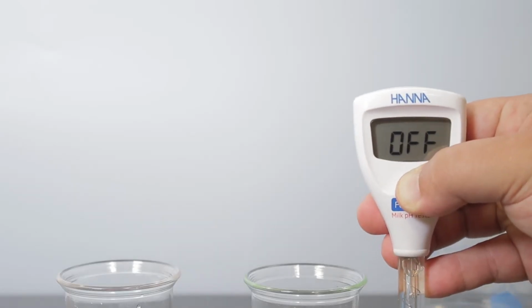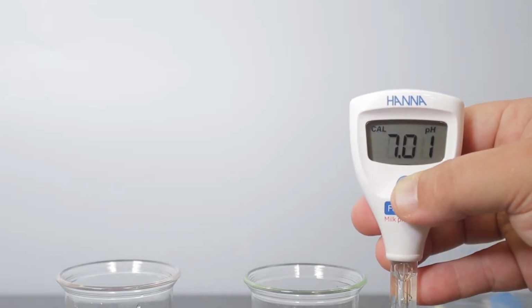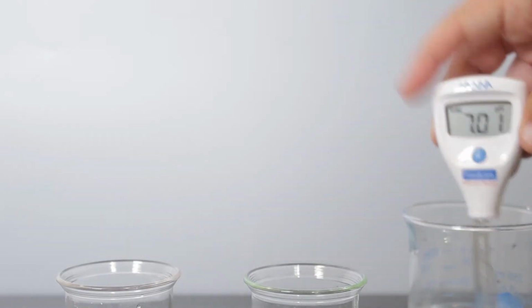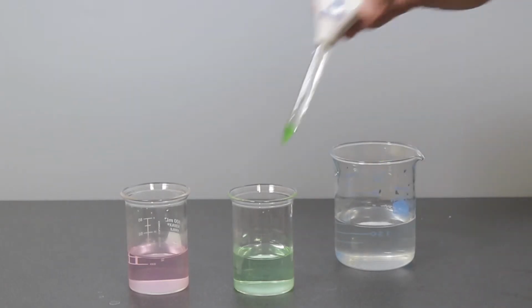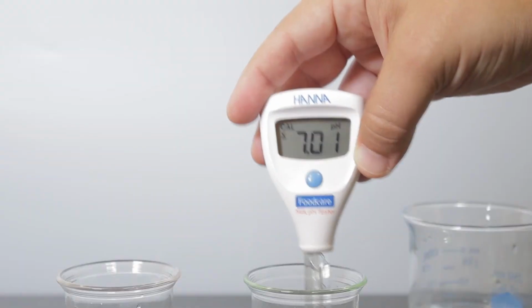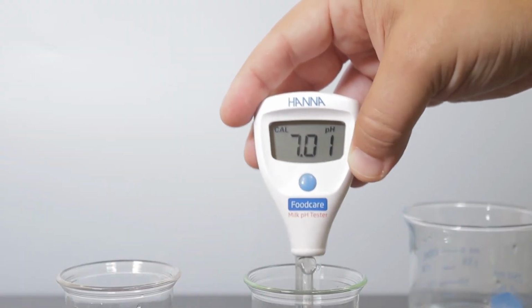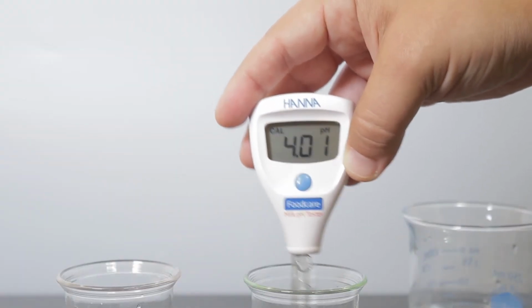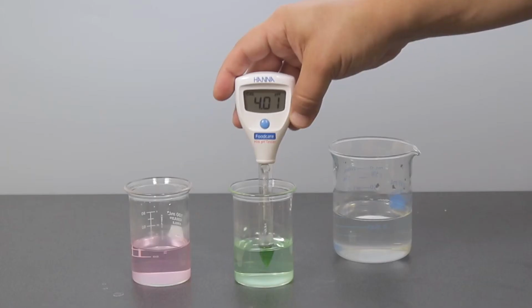Calibration is an important step in ensuring accurate results. We recommend calibrating before each use. To calibrate your tester, press and hold the button for 3 seconds until Cal appears on the screen. Rinse the electrode in deionized water and place the tester in your pH 7.01 buffer and wait for a stable reading. Once stable, the tester will automatically store the calibration and prompt you to use pH 4.01 buffer.